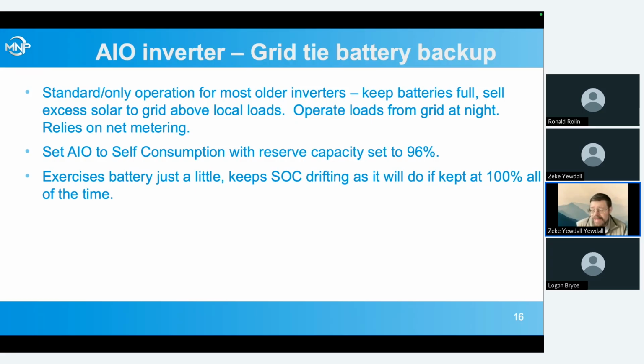And if that current draw from the battery is below a certain level, the BMS doesn't see it. Typical BMS, if it's under 1 amp of DC current, and this is not just our batteries, this is pretty much all lithium batteries, the BMSs are not that accurate at low amperage. They're not as accurate as the old amp hour counting meters like a Trimetric or a Victron Smart Shunt. So if they have less than 1 amp of current, they just don't see it. And if you've got one of our inverters and 2 or 3 batteries, each battery sees less than 1 amp of current.